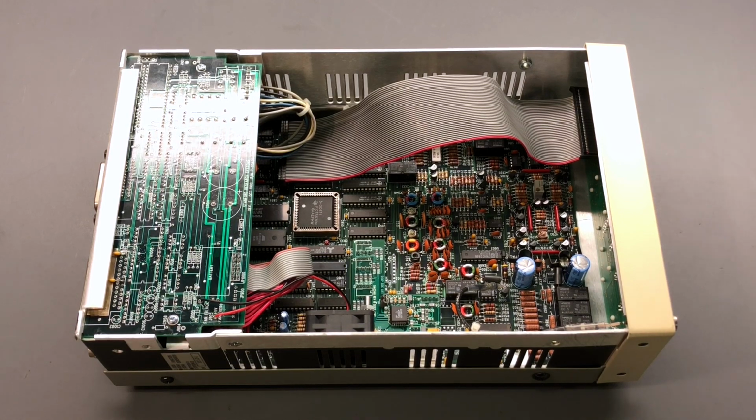So the way that Stanford Research Systems has set up the calibration in this instrument is that there are a few select physical adjustments that are done on the main circuit board, but the majority of the adjustments for calibration are done in software by calibration factors. Stanford Research Systems uses the term CalBytes, C-A-L-B-Y-T-E-S, okay, so CalBytes. And there are literally hundreds of these CalBytes, or correction factors, that are permanently stored in ROM, which is read-only memory.